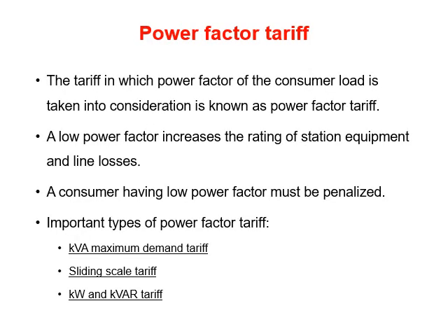And then the next one is the power factor tariff, the tariff in which the power factor of the consumer load is taken into consideration. A low power factor increases the rating of station equipment and line losses. So a consumer having a low power factor must be penalized. That is, they have to pay a penalty charge.